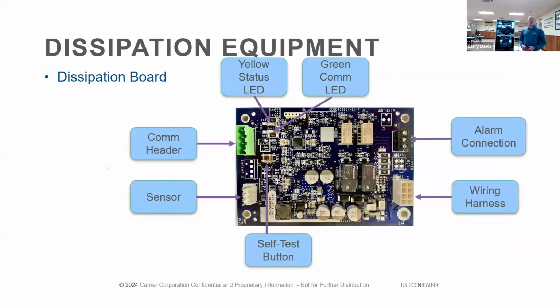I look at the mitigation or the dissipation board. It's the same board regardless of what equipment you're using across the product line, whether it's the basic series or builder's models, the mid-tier, or the communicating system. The dissipation board's the same. You have a plug for the sensor. You have a plug for the wiring harness. You do have an alarm output. So if you wanted to hardwire an alarm to something, say to have a light go off if there's a dissipation taking place, you can do that.